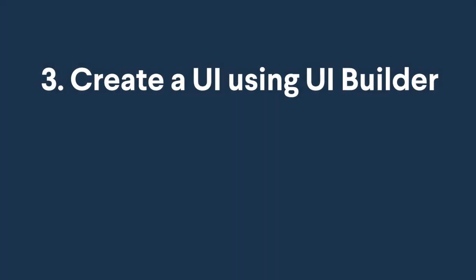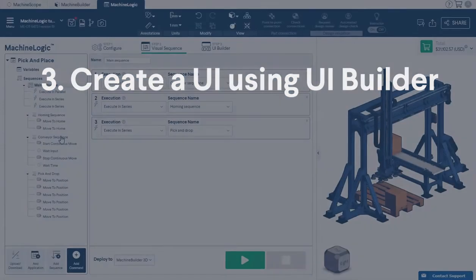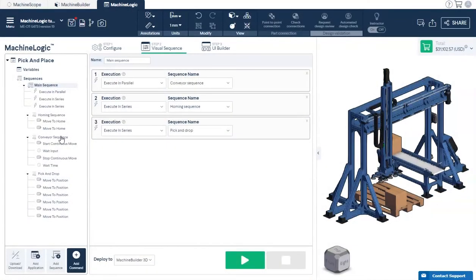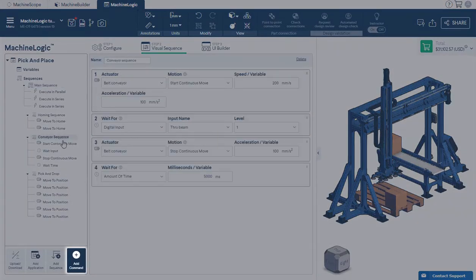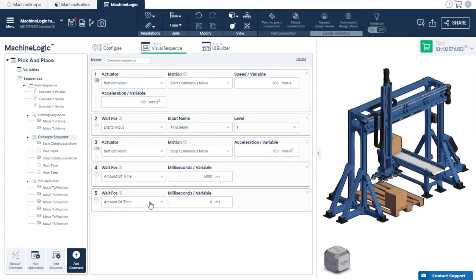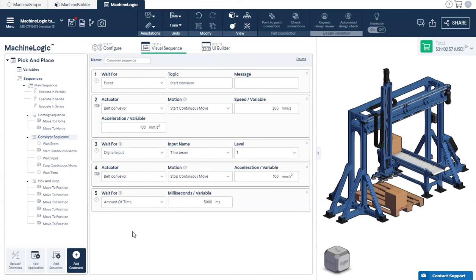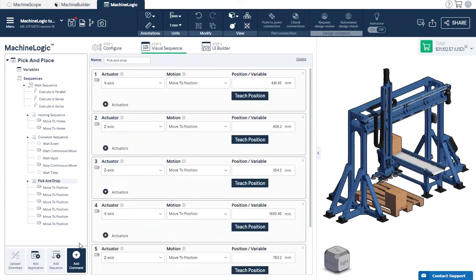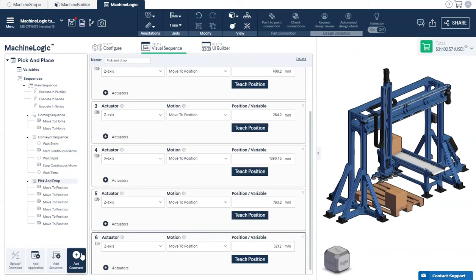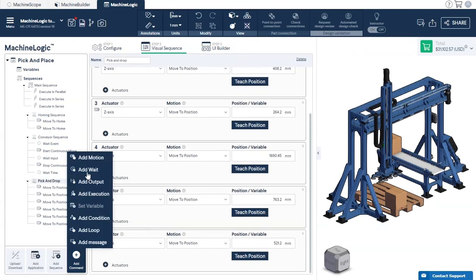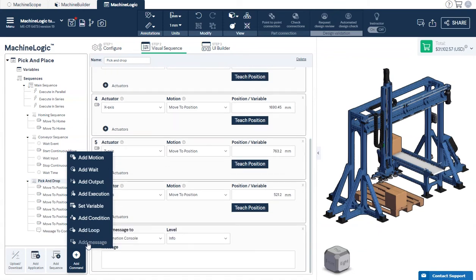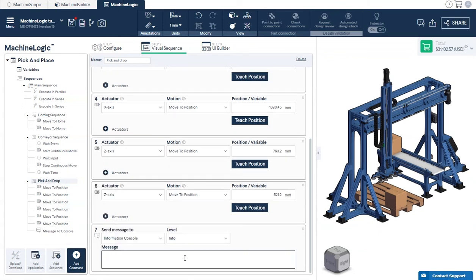Step 3: Create a UI using UI Builder. Now that you've built your MachineLogic program, we can create an operator interface for that application. We'll first edit our visual sequence to trigger only the conveyor child sequence when a button in the UI Builder is pressed. To do so, we'll add a wait for event command at the very top of the child sequence. To generate a message to the UI Builder, click add command and add message to let the operator know when the pick and drop child sequence is completed.